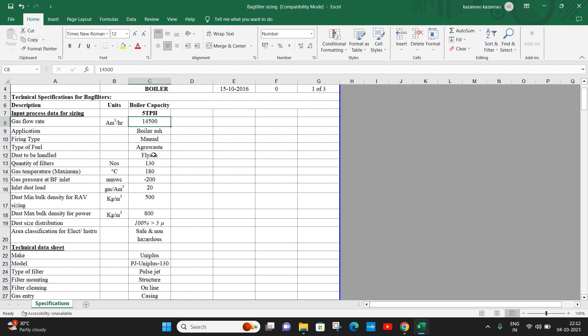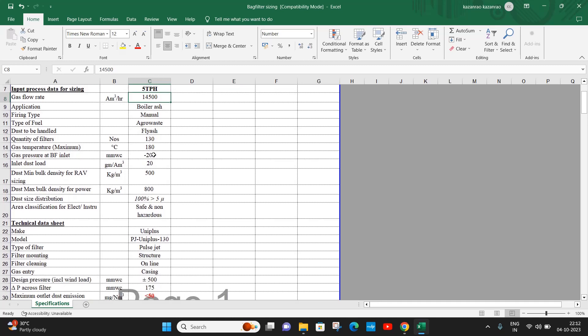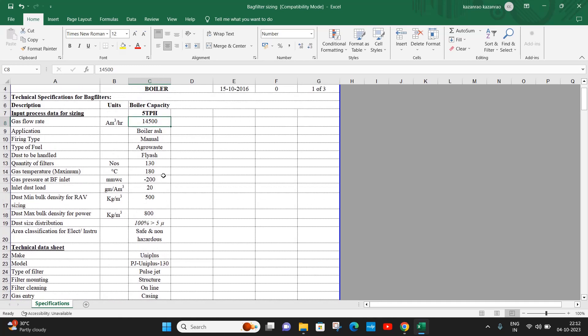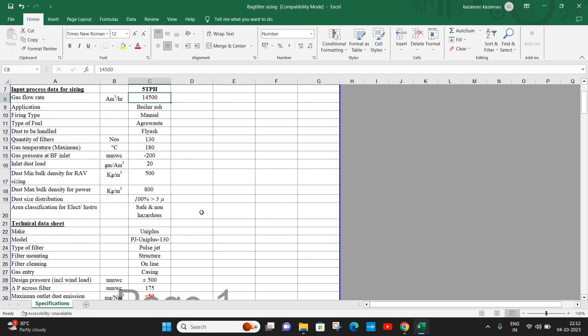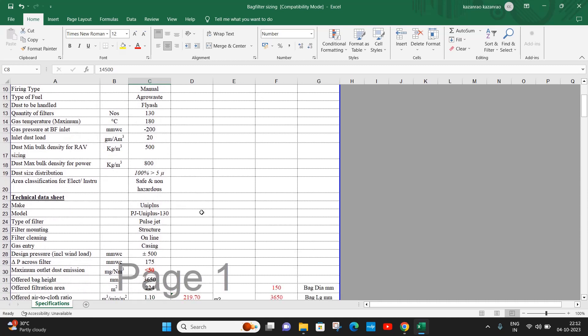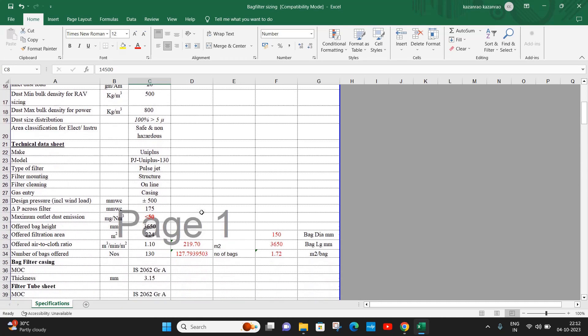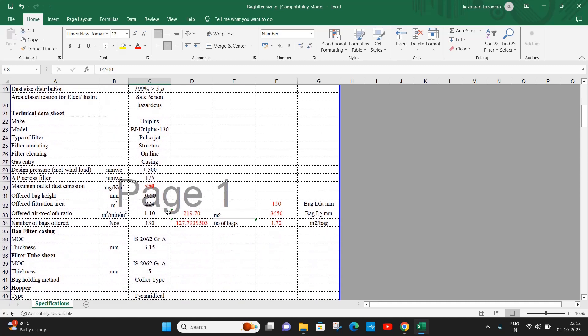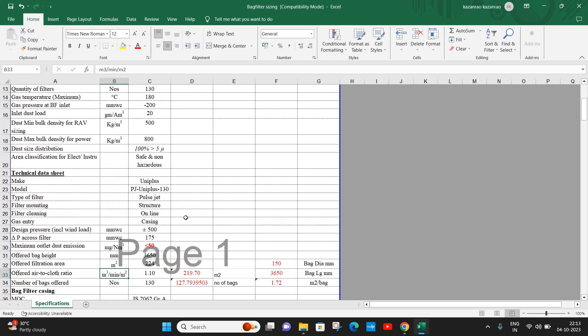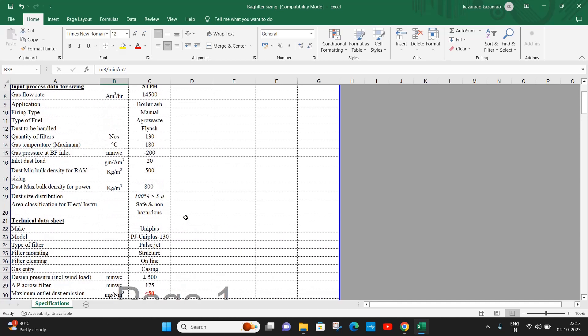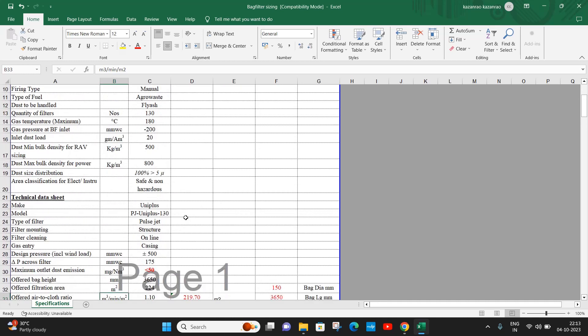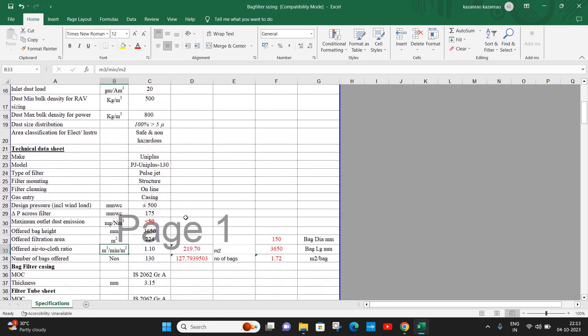This is the complete specification. However, our interest is to know how the bag filter is sized based on the air to cloth ratio. Now let us go to the air to cloth ratio. It is 1.1 meter cube per minute per meter squared. The gas volume here is 14,500 meter cube per hour.